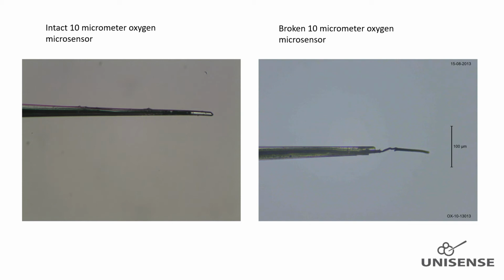A broken sensor will in water give a very high signal, typically out of range, as the working electrode is now directly exposed to the sample. So, if the tip breaks during measurements, a sharp signal rise will occur to the out-of-range level. Sometimes the sensor does still respond to oxygen because the exposed working electrode can still reduce oxygen, but it will be very unstable. It is not possible to repair a broken sensor.